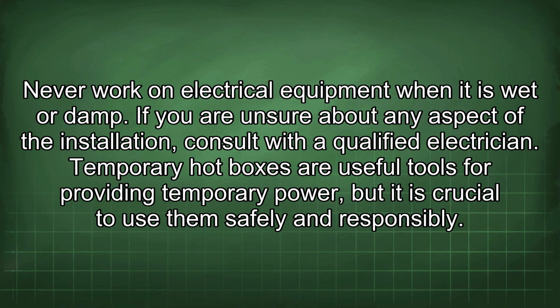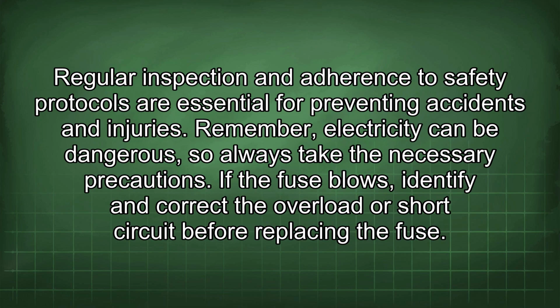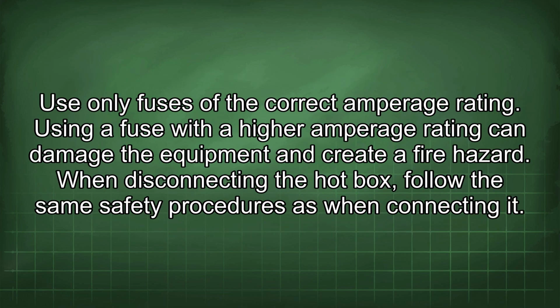Temporary hotboxes are useful tools for providing temporary power, but it is crucial to use them safely and responsibly. Regular inspection and adherence to safety protocols are essential for preventing accidents and injuries. Remember, electricity can be dangerous, so always take the necessary precautions. If the fuse blows, identify and correct the overload or short circuit before replacing the fuse. Use only fuses of the correct amperage rating. Using a fuse with a higher amperage rating can damage the equipment and create a fire hazard.